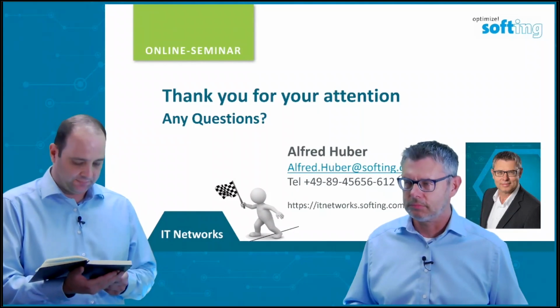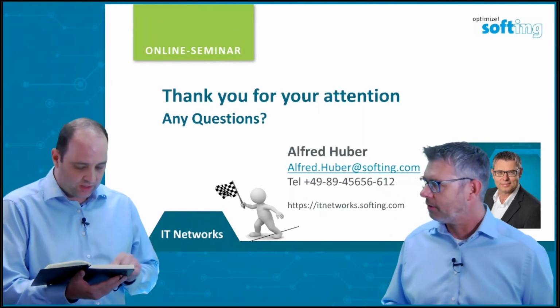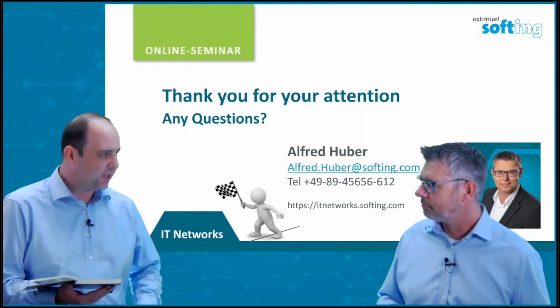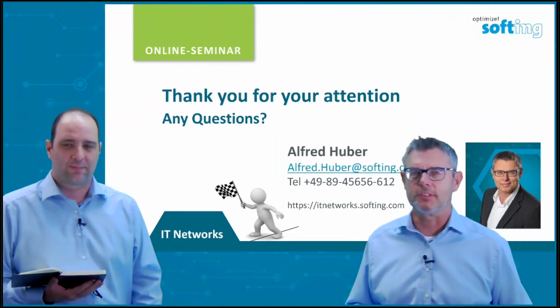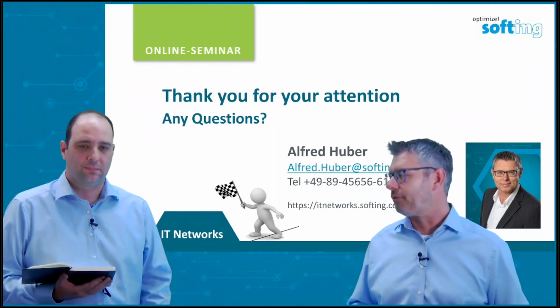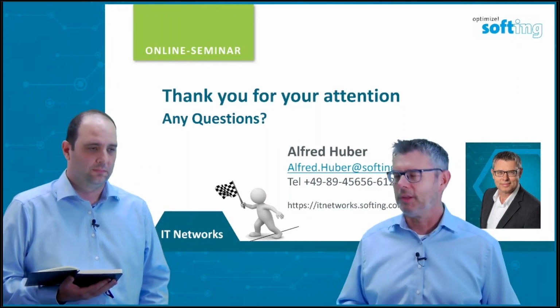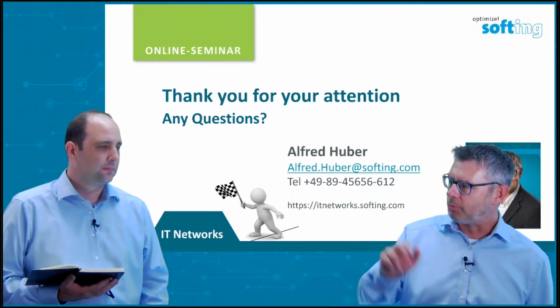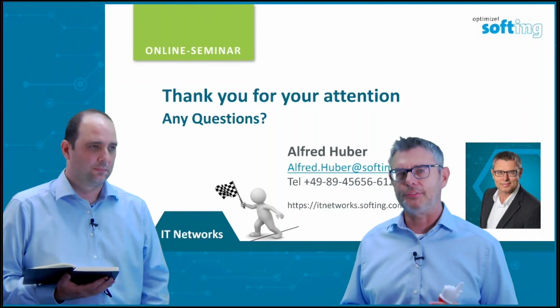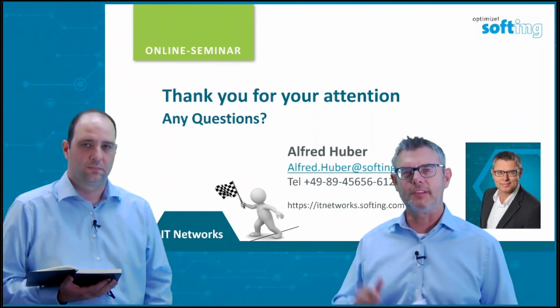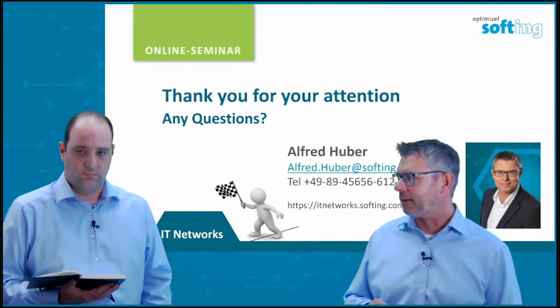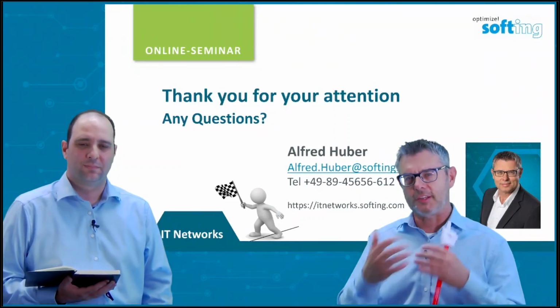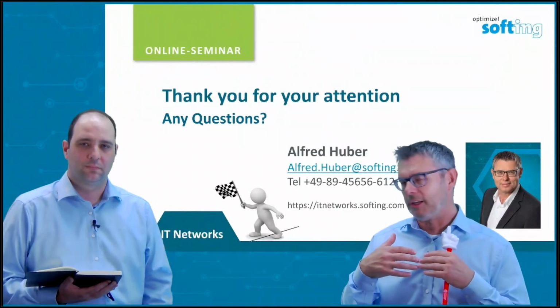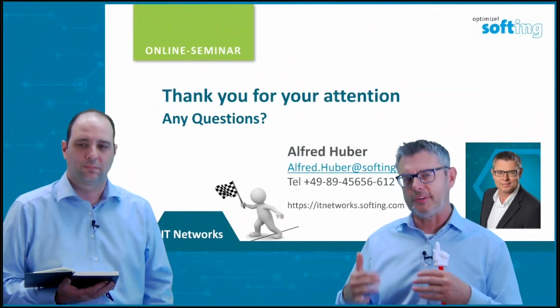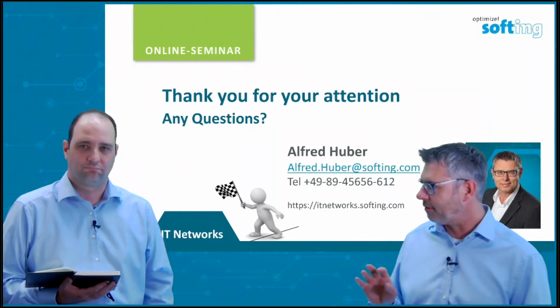Then there was the question about the LinkXpert M3. What does it do on fiber? Is it doing a qualification on fiber? What the LinkXpert is doing is, first of all, it can definitely qualify the end face, as you have seen with the picture on the microscope, and it can also get in contact with a network that is fiber optic based. So it's an active test, as you will see next week on Thursday, what an active test instrument can do. It's like getting in contact with the switch and asking for an address, DHCP testing, ping testing. So a certain number of active tests. It does not do any passive testing.